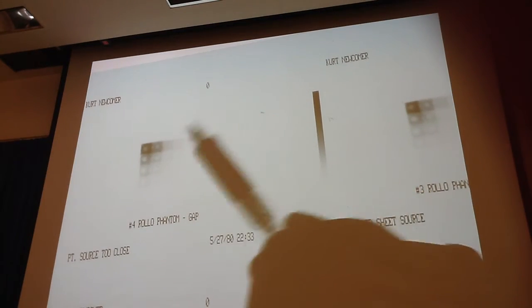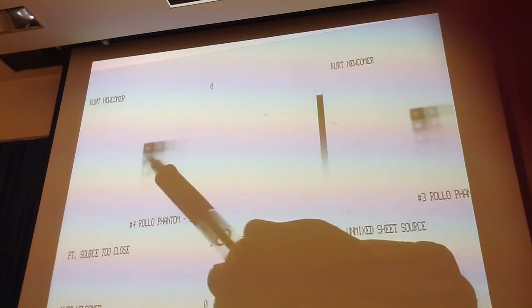So we actually have a phantom in here that's designed to represent a 25% change between the number of counts it collects. So in other words, there would be 100 counts here, 75 here, 50 here, 25, so they have different numbers of counts in here to represent the different shades of gray and colors that you would have on your film.